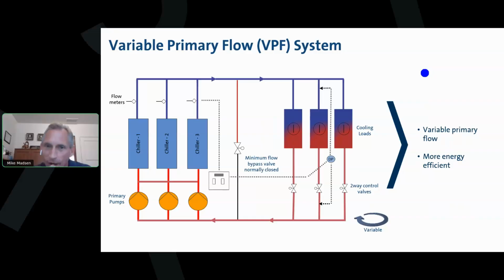So we'll do a quick review of how systems are done today. A very common one is variable primary. So with variable primary, you've got big primary pumps or a big primary pump skid, high head, so they're high head pumps. Their job is to keep the chiller happy. And the reason they're high head is they need to supply enough head pressure to satisfy the furthest zone in the system, or the index zone. We're maintaining some delta P out there.